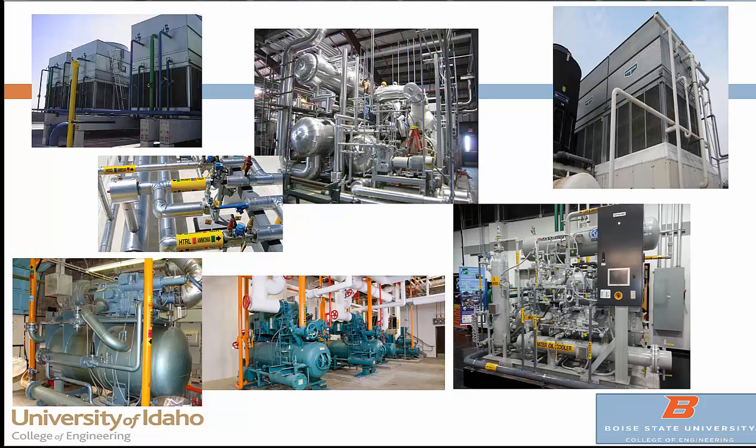In reality, industrial plants can be messy — you may or may not have color coding, and it can take considerable patience and time to figure out which compressor is doing what. The first time I did one of these assessments at a big plant in Pocatello, I was literally blown away. For ammonia systems, labeling is required, and once you learn the jargon and abbreviations, it becomes easier to follow the main path of the refrigerant.